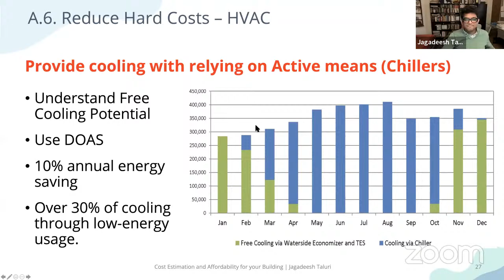The chart on the right side shows, in the green shaded bars, where we will be able to use free cooling via a water side economizer over a year. So during these months and these many hours, we will be able to run the building without actually using a chiller. This could potentially reduce your annual energy by 10%. You can also reduce your cooling energy by 30% in a climate like Gurgaon, and if you're in a benign climate, you'll see far more benefits.